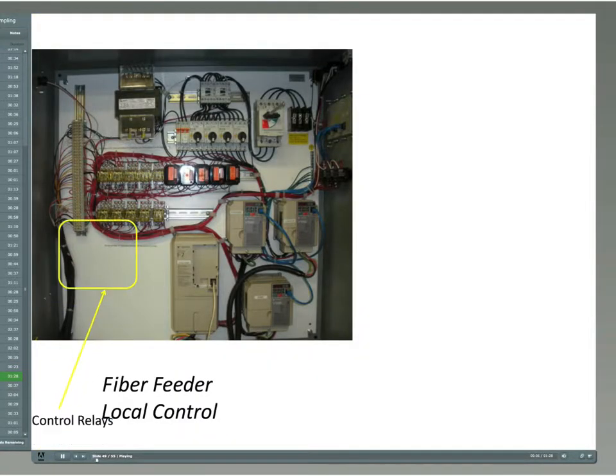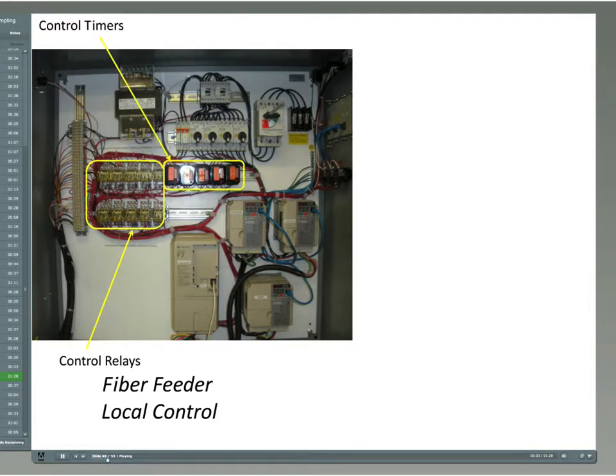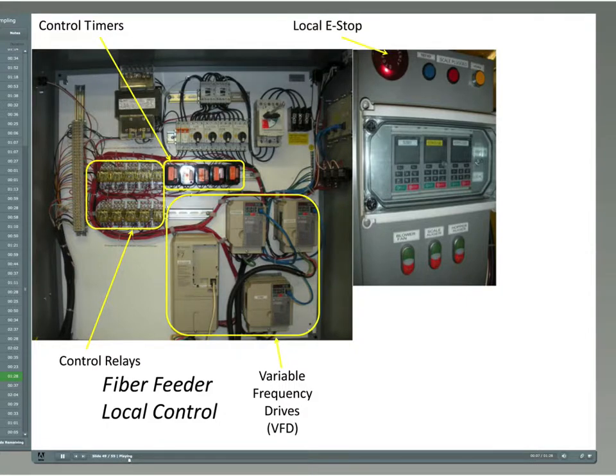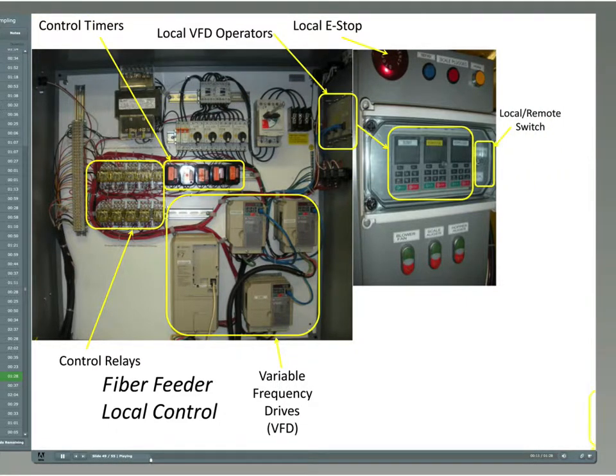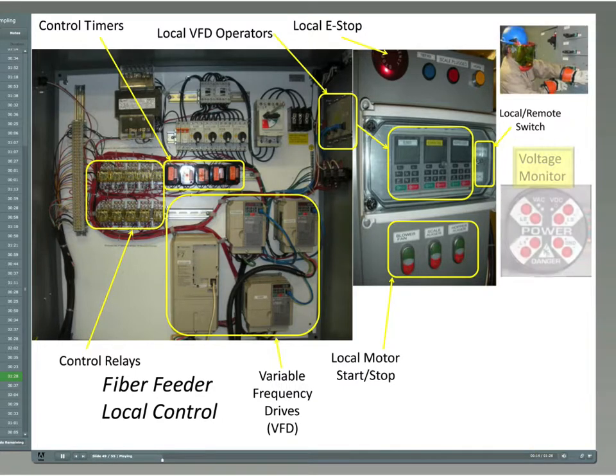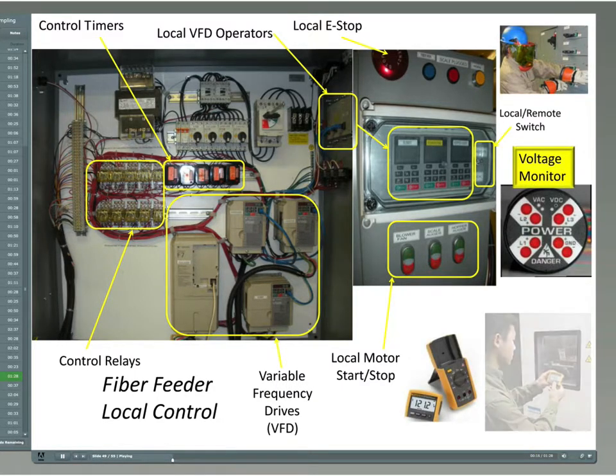This enclosure has 480 volts AC and enough power to warrant an 8-calorie suit. A voltage monitor is wired to the voltage source. Power may be considered to be disconnected once the circuit breaker feeding the panel is disconnected, while observing the once illuminated lights now extinguishing. While using a wireless meter, the technician on the bottom right is troubleshooting inside his power panel.